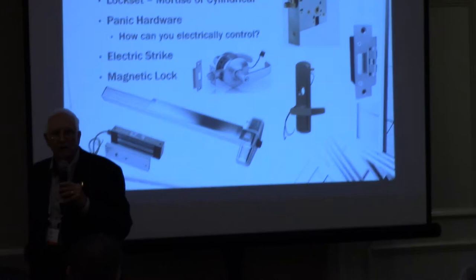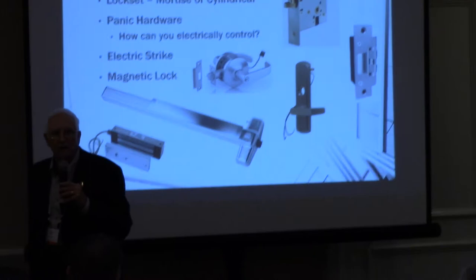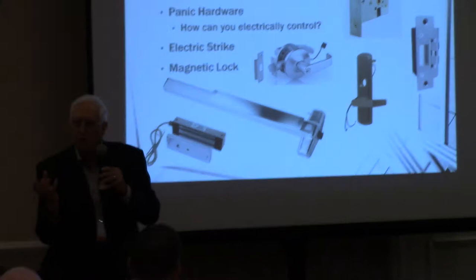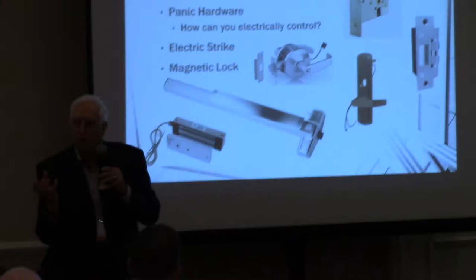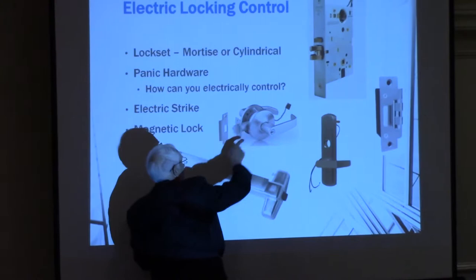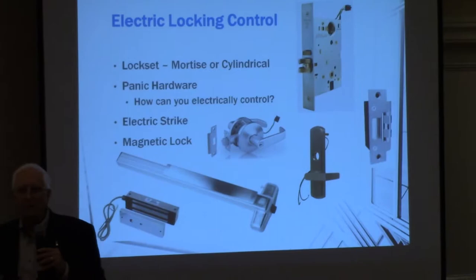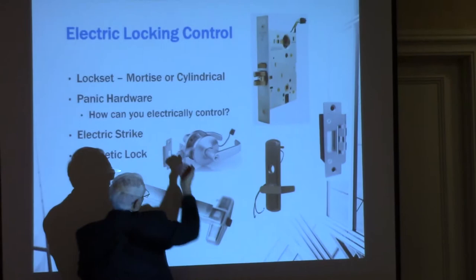On a rated door it's really important to remember that you have to latch. If you retract the latch electrically and someone mis-programs the system and it gets stuck in the retracted position, the door is not rated. You'd have to tie it into the fire alarm so it re-latches. With electrified trim, the door always latches. Magnetic locks — a face-on mag lock is the most tolerant of a racked door; a shear lock is the least tolerant.